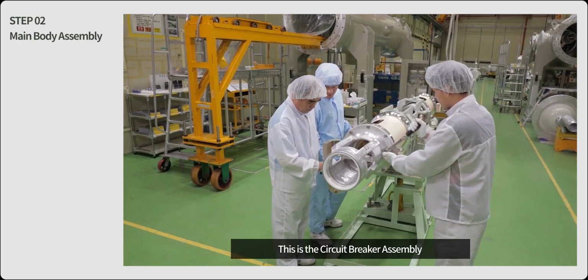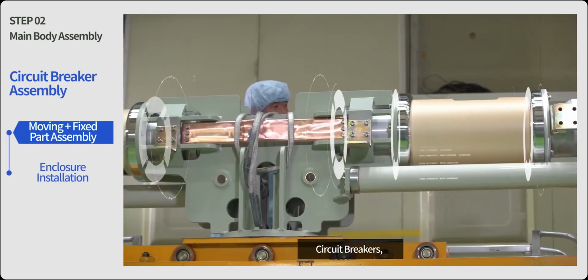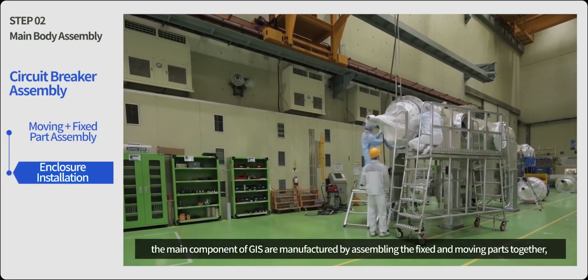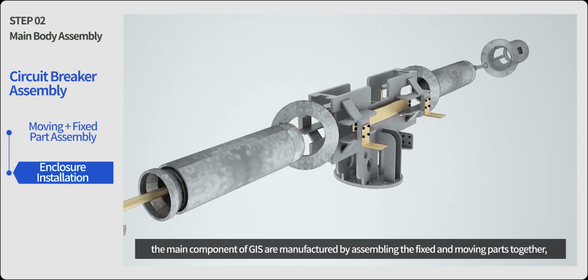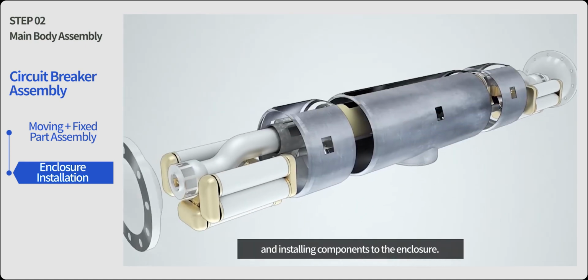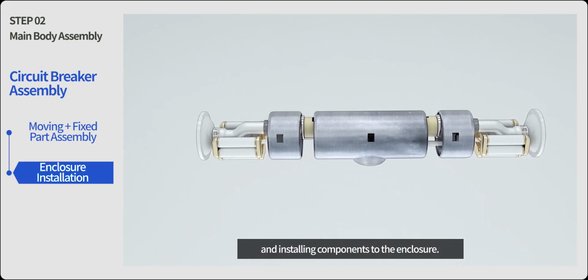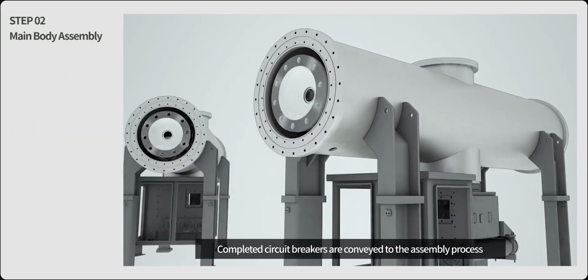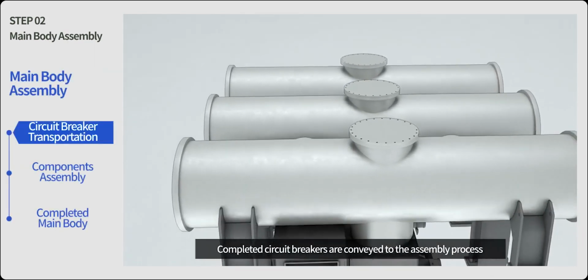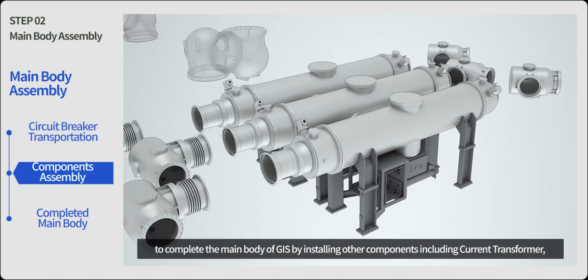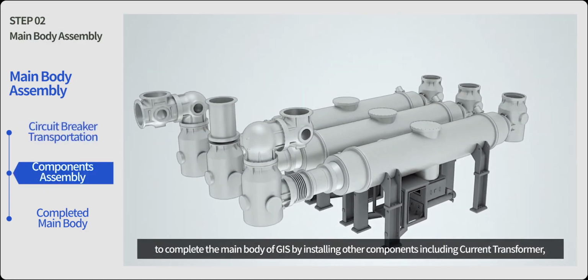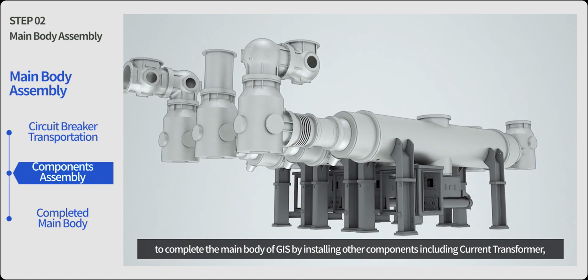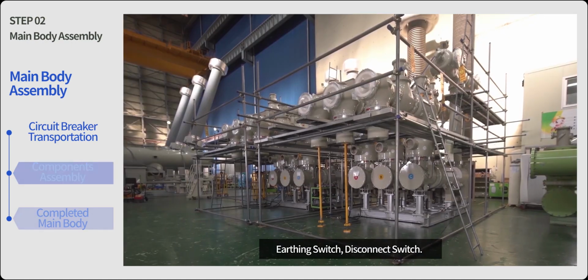This is the circuit breaker assembly. Circuit breakers, the main component of GIS, are manufactured by assembling the fixed and moving parts together and installing components to the enclosure. Completed circuit breakers are conveyed to the assembly process to complete the main body of GIS by installing other components, including current transformer, earthing switch, and disconnect switch.